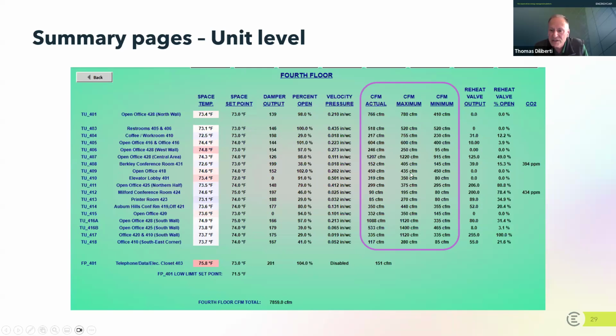And if you read down this list, again, you might find some consistencies, some inconsistencies, but the main teaching point in this particular screen, all of these things are part of the MEP documents when you get a building. What I would strongly recommend you do if you have sophisticated systems like this is you have to compare these values that are programmed into your system with the values for how the system was designed to operate. You'll see it in a table or a chart. These values were designed by the designer of the building to run at certain levels.